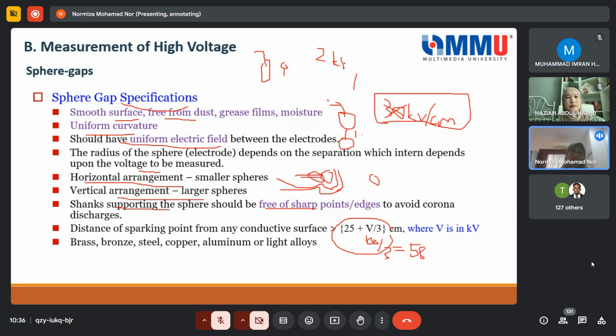And sometimes if you're not sure, because otherwise we have to calculate for every equipment, so we use 2 kV per cm. But if the equipment always causes sparking and so on, then we use 1 kV per cm or even lower, 0.5 kV per cm. So if I apply 100 kV, it means the person or the other equipment has to be 50 cm away. But this one is even more actually. They use 25 plus V/3. If you apply 100 kV, it means the person or the equipment has to be at least 58, or in other words, round up to 60 centimeter. It means the person has to be 60 cm away from the equipment under test.